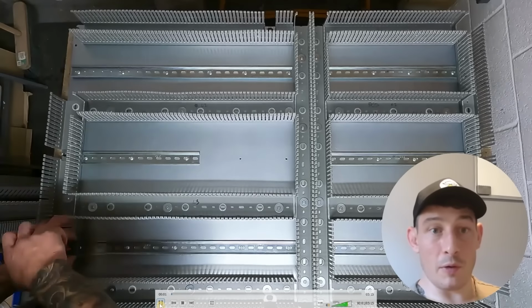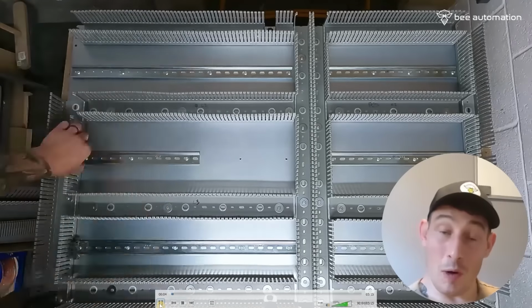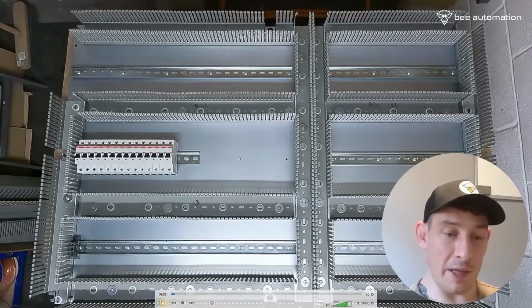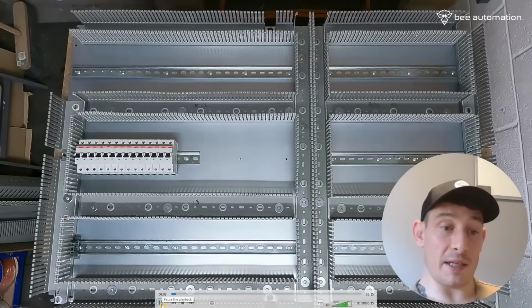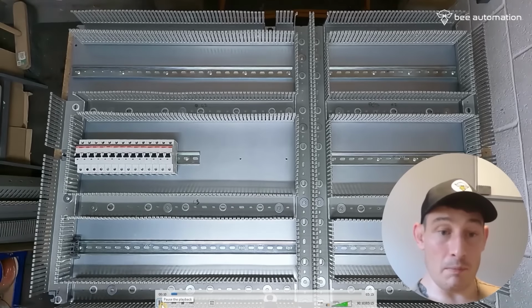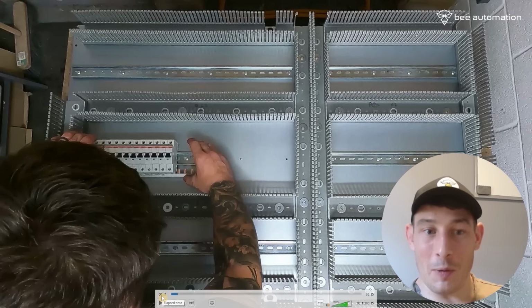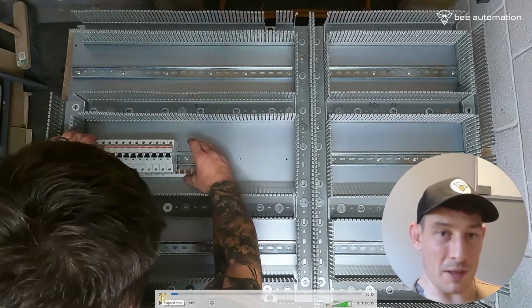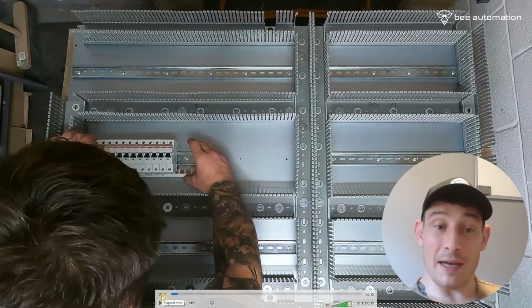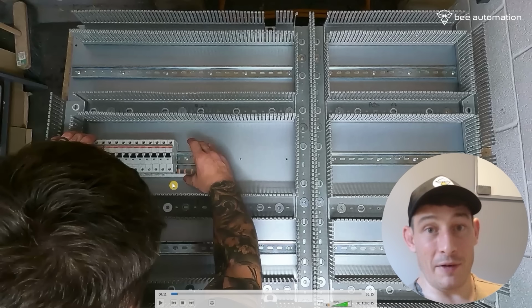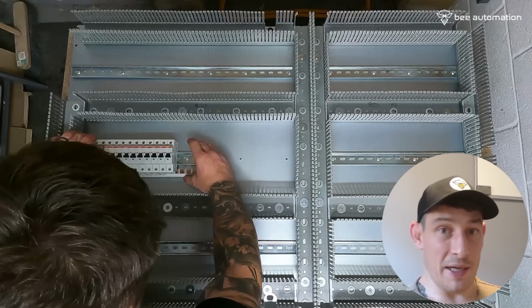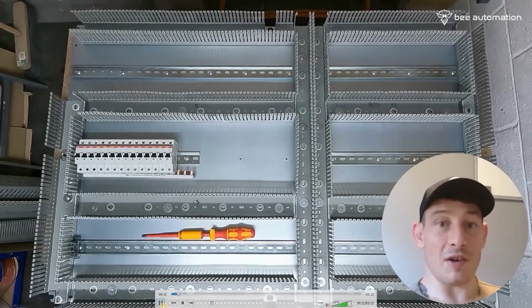Okay guys, on to fixing the components, one of my favourite parts. So starting off with the MCBs, initially fixing the busbar to the bottom. Now I've had a lot of people tell me, oh, you shouldn't fix busbars to the bottom, or you shouldn't fix busbars to the top. End of the day, it comes down to the MCB and the manufacturer, so check in the manual which way you should fix the busbar. A lot of them it doesn't matter, and with these ABB MCBs, it doesn't matter. So I initially decided to do it at the bottom.